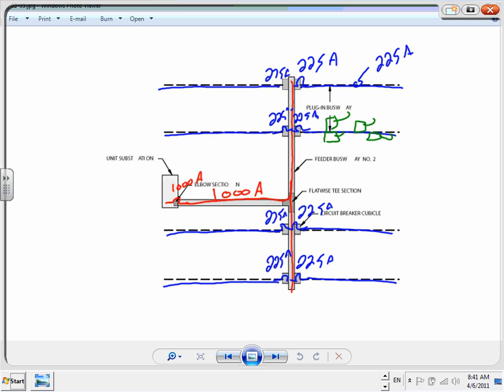wire. Later on, you're going to circuit the disconnect to the plug-in busway, and the plug-in busway to the feeder busway. Did you guys hear me? In Revit, first you're going to draw this. We have a family for all of this stuff. Second, you need to put an overcurrent protection device, which is right here. It's going to look something like this. Basically, an overcurrent protection device right next to these, the main for each one of these. That's easy to do in Revit: a disconnect with an overcurrent protection device.